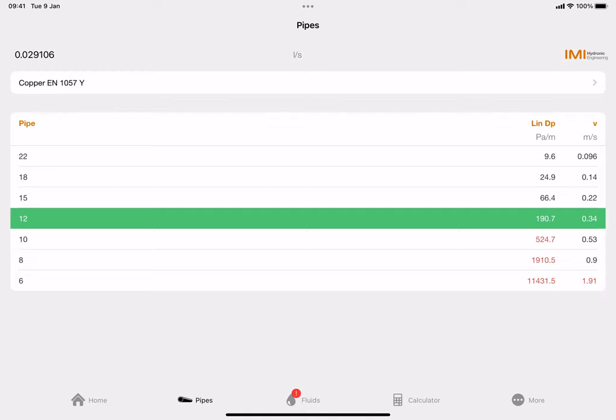The way I like to describe this: imagine a 300 millimeter length of 15 millimeter pipe sticking vertically, and then a thousand slightly shorter lengths of pipe work - going from 290 millimeters, then 285, and so on right the way down both sides, maybe two thousand in total, all joined up with a bit of 28 millimeter pipe underneath. If you've got a pump that can overcome that tallest piece of 300 millimeter pipe in the center - you can visualize this - that water will come out of all the others. It doesn't matter if there's five a side or a thousand a side: as long as you're getting over that one in the center, that's your index circuit.